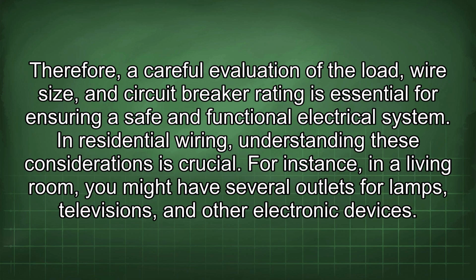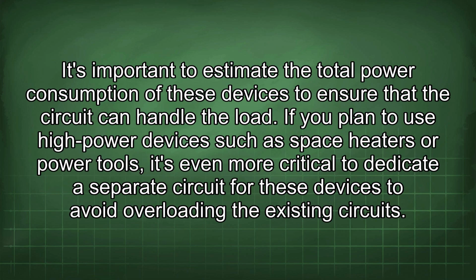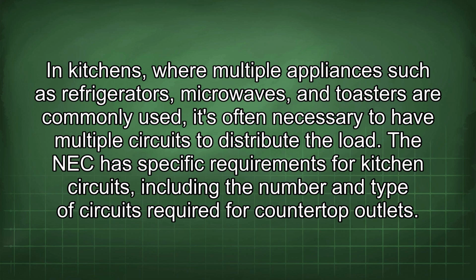For instance, in a living room, you might have several outlets for lamps, televisions, and other electronic devices. It's important to estimate the total power consumption of these devices to ensure that the circuit can handle the load. If you plan to use high-power devices such as space heaters or power tools, it's even more critical to dedicate a separate circuit for these devices to avoid overloading the existing circuits. In kitchens, where multiple appliances such as refrigerators, microwaves, and toasters are commonly used, it's often necessary to have multiple circuits to distribute the load. The NEC has specific requirements for kitchen circuits, including the number and type of circuits required for countertop outlets.